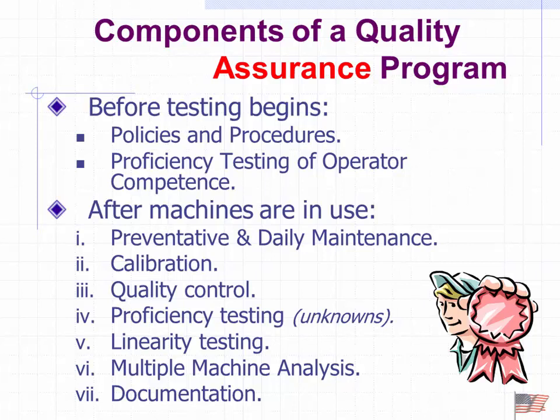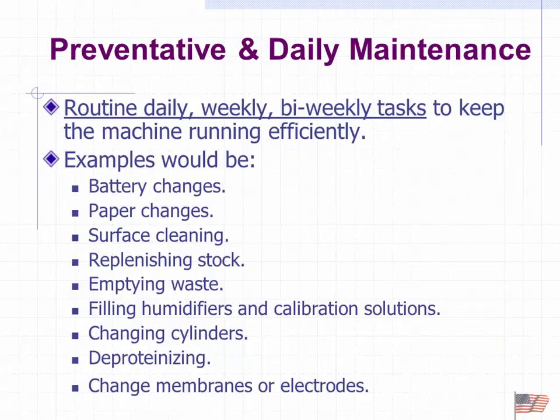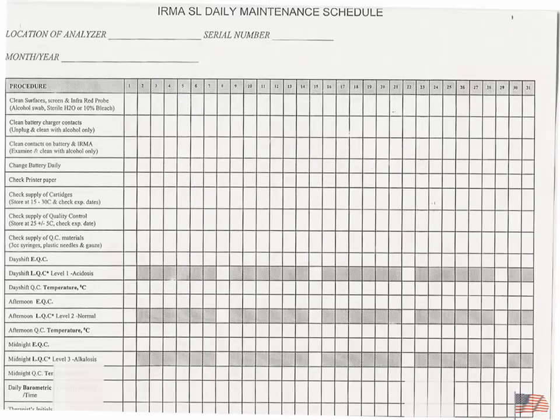Then there needs to be a whole bunch of stuff that we're going to do on a periodic basis. Let's go through them. First of all, we're going to do some daily or periodic maintenance. If there's a battery that needs to be changed, or a solution that needs to be changed, or a calibrating gas that needs to be changed, or the waste container is getting full, I need to empty that out, and various other stuff. Changing the membranes that are on the electrodes, those semi-permeable membranes may need to be changed, or the electrode itself may need to be changed. And we keep a log of it. When was the last time we emptied the waste bottle? Oh, it's been 4 days. I'm going to make a bet that that's probably overflowing, right?